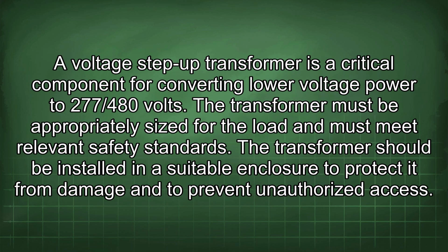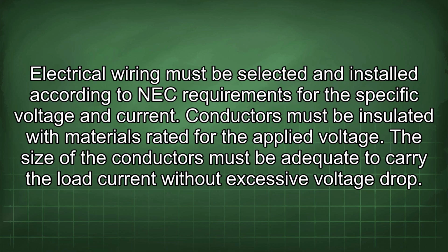A voltage step-up transformer is a critical component for converting lower voltage power to 277/480 volts. The transformer must be appropriately sized for the load and must meet relevant safety standards. The transformer should be installed in a suitable enclosure to protect it from damage and to prevent unauthorized access. Electrical wiring must be selected and installed according to NEC requirements for the specific voltage and current. Conductors must be insulated with materials rated for the applied voltage. The size of the conductors must be adequate to carry the load current without excessive voltage drop.